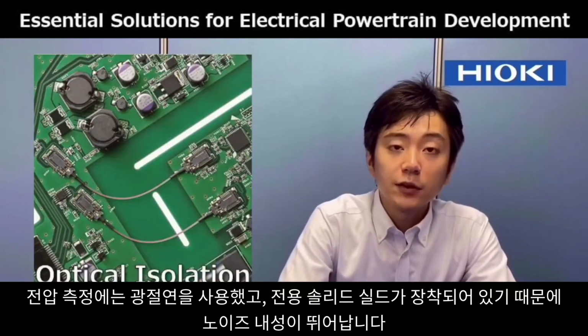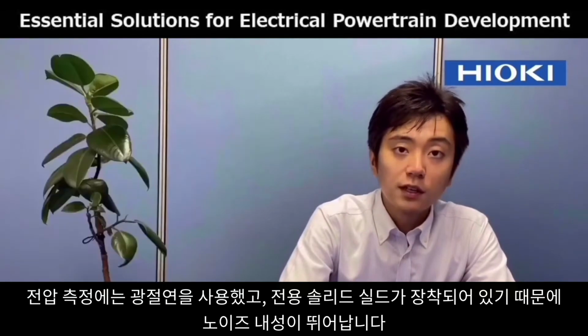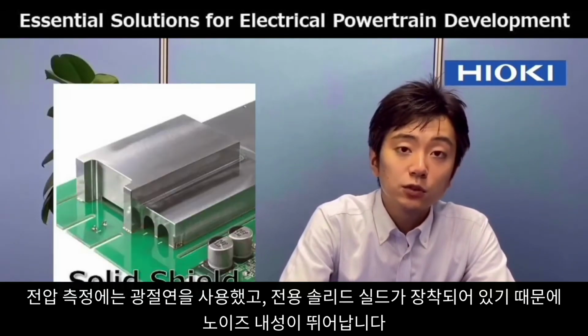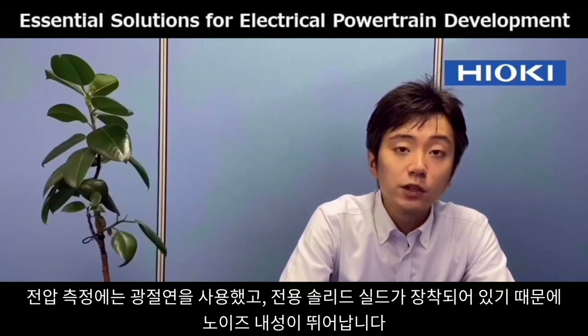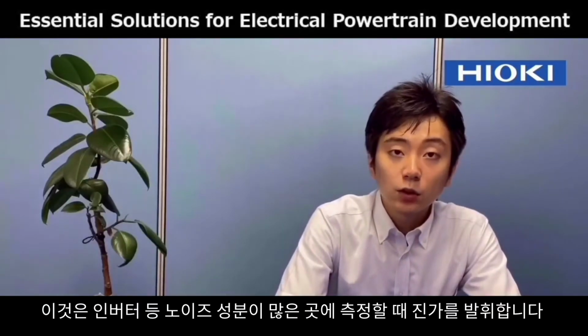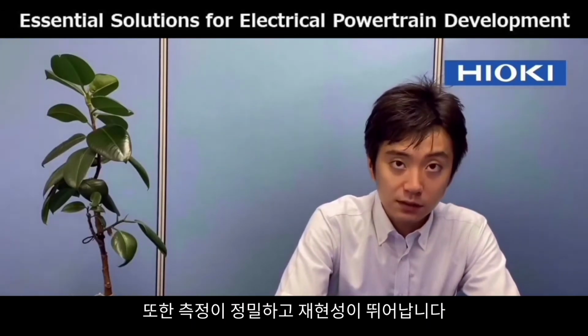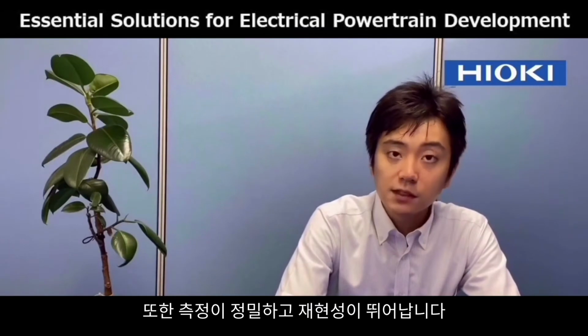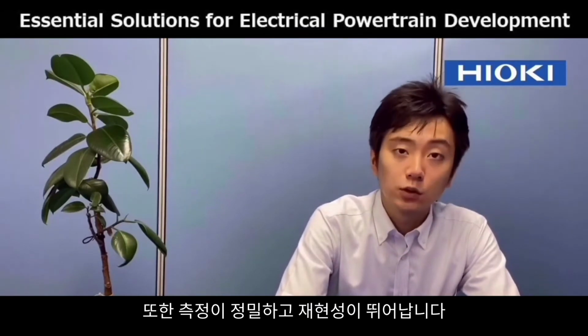As for noise resistance, optical insulation is used for voltage measurement. In addition, the original solid shielding provides excellent noise resistance. This is great for measuring close to machinery like inverters that give off a lot of noise. All of this makes this power analyzer's readings highly accurate and highly reproducible.